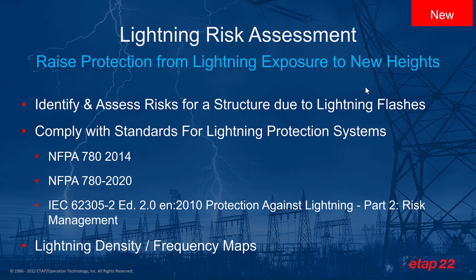Another new capability that we've added to our safety portfolio is lightning risk assessment. Lightning risk assessment allows us to raise the protection from lightning exposure into new heights. And we can do so by identifying and assessing the risk for a given structure due to lightning flashes or lightning incidents that may happen around that area. The lightning risk assessment calculator allows us to comply with standards for lightning protection systems such as NFPA 780, 2014 and 2020 standards, as well as IEC 62305 edition 2, which gives us the ability to define protection against lightning and do certain risk management.